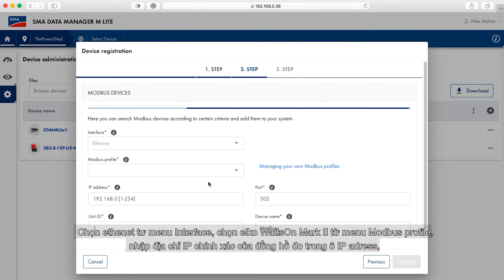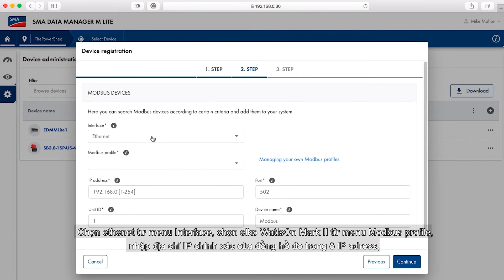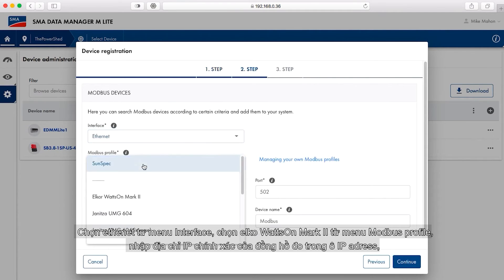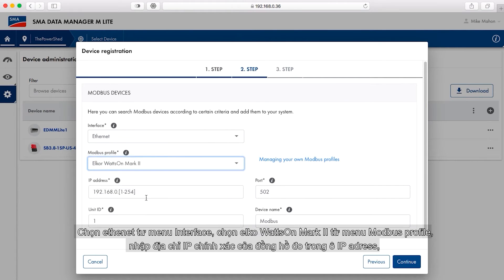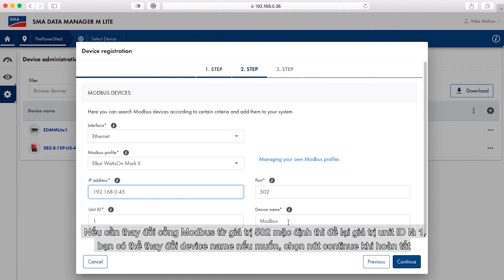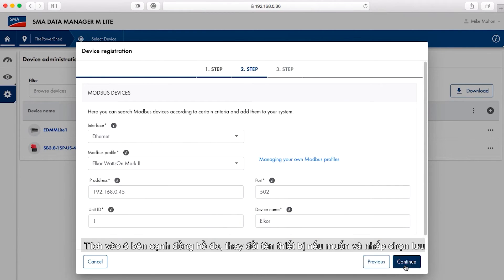Select Ethernet from the interface drop-down menu. Select Elkor WattsOn Mark II from the Modbus profile pull-down menu. Enter the correct IP address for the meter in the IP address window. If needed, change the Modbus port from the default 502 value. Leave the unit ID as 1. You may change the name if desired. Select continue when done.